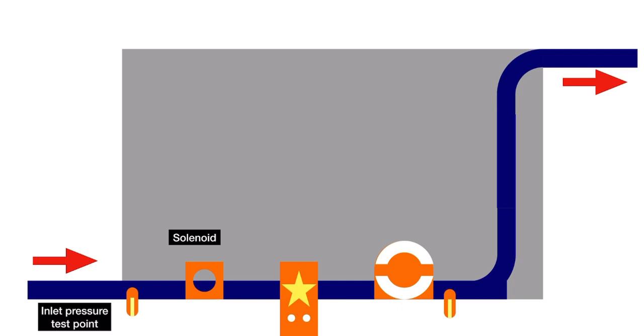It's an on-off switch, which allows gas into the rest of the valve. If the solenoid is open, the gas then goes through to the FSD, the flame safety device, and ignition, which are generally all one unit. And again, you can see here, I've got this poking out of the multifunction valve. And this will be the buttons that you see sticking out. You've either got one big red button or a couple of buttons, one of which will be the ignition and the other one will be the FSD. But these are the buttons that you hold in to light the appliance and then allow the FSD to warm up.